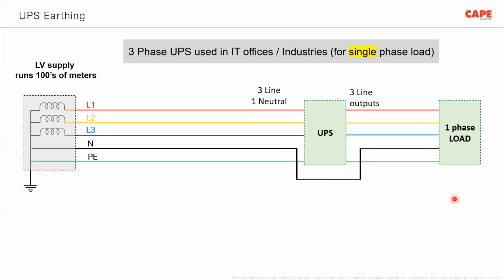Often I don't understand how this system works. That is a different scenario. But now this is how we use it in a lot of installations. Common neutral is shared for single-phase equipment. From the load point of view, it looks okay, but it is not at all safe. Whenever there is an overload or a short circuit in the load, it will be a disaster. It can catch fire.